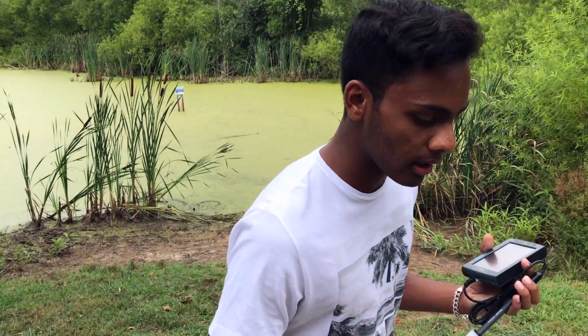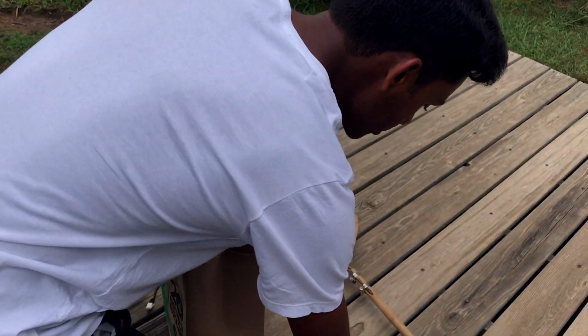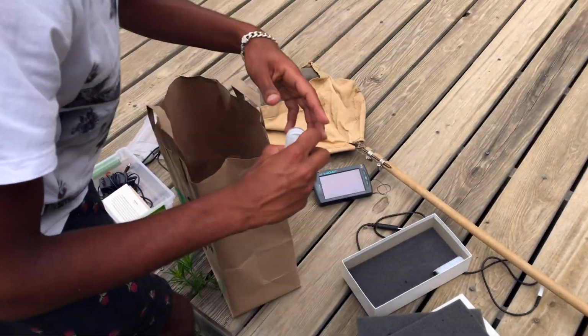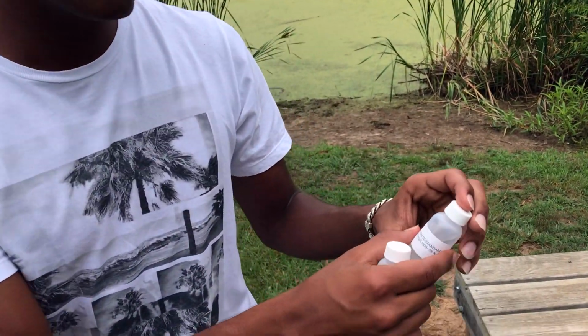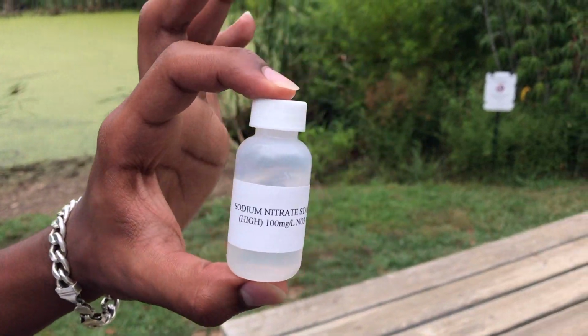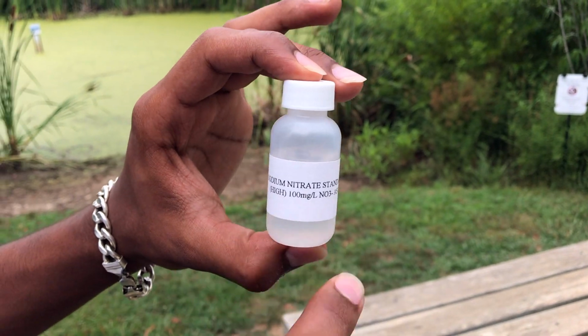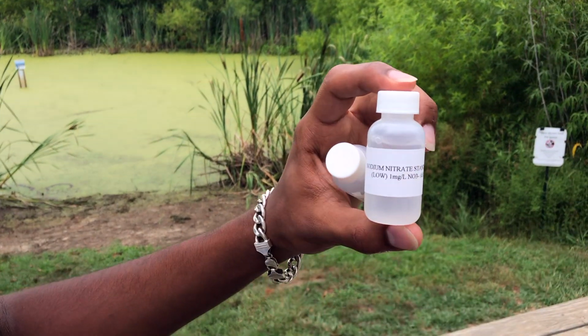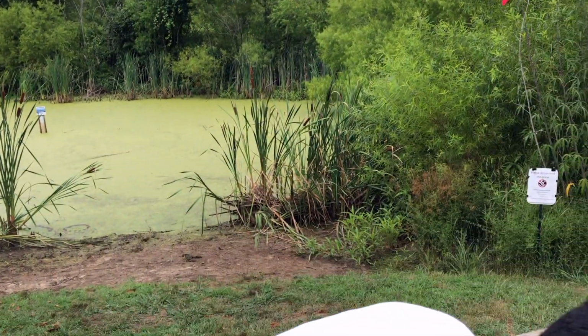Next up for our nitrate probe, which is not common for any of the other probes, is calibration. Calibration is extremely important for these ones, and usually the box will come with calibration items. Here we have the high end of the calibration, sodium nitrate, 100 milligrams per liter, and this one is our low of 1 milligram per liter. So we can go ahead and use these for our calibration testing.